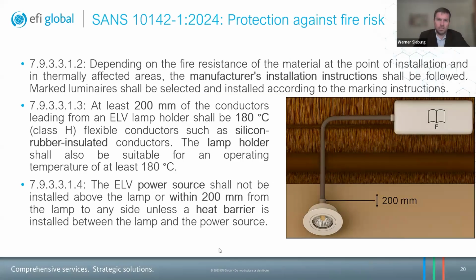So marked luminaires shall be selected and installed according to marking instructions. So if there's a marking on the lamp specifically that states you have to keep this such a distance away from flammable materials or combustibles, that needs to be taken into account.